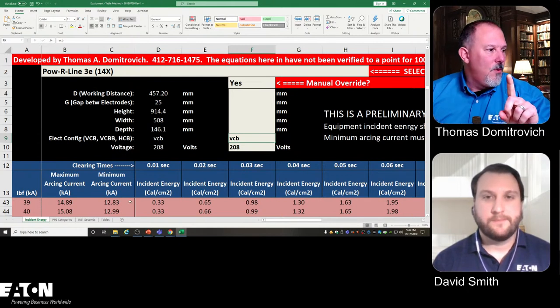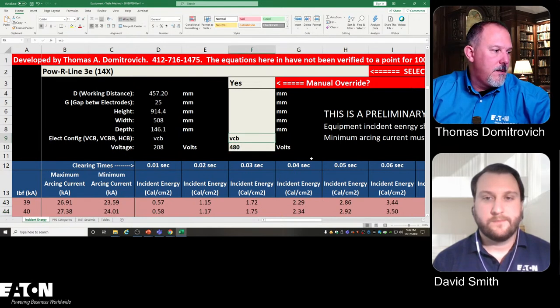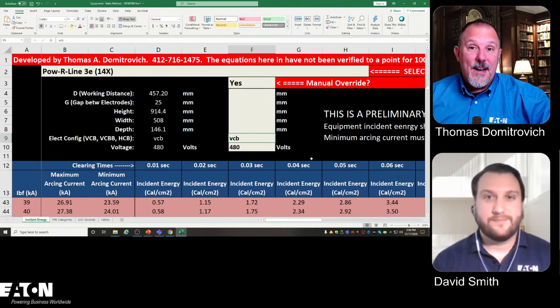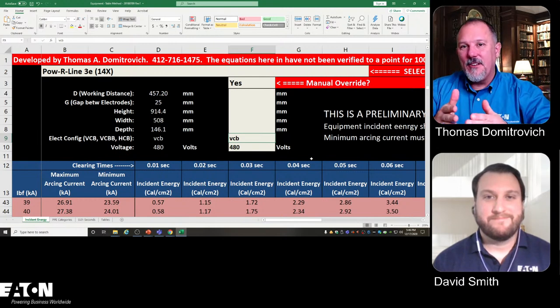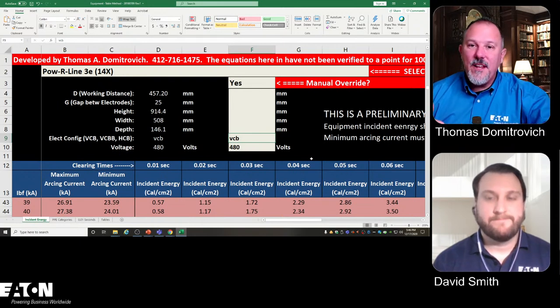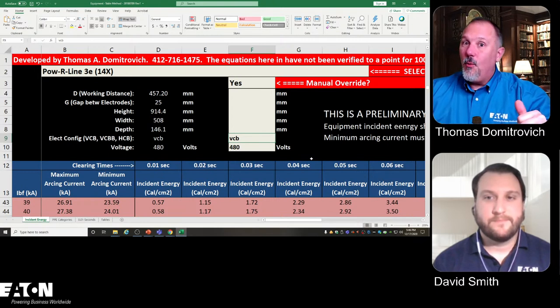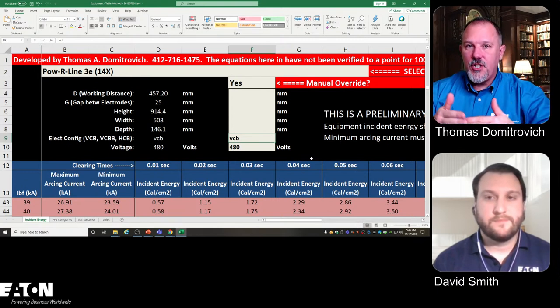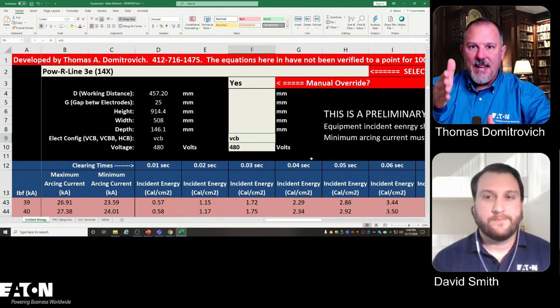Right. But look what happens to the arcing current. At 208 volts, my lowest arcing current is 12.99. Okay. Let's put this at 480. It goes to 24,000. It cut it in half. Now, think about the time current characteristic curve for a circuit breaker. When I have a lower voltage, my arcing current got cut, went from 24,000 to 12,000. It went way to the left. I have a better chance of being in the long time region on that same, I haven't changed, it's still a 600 amp breaker.